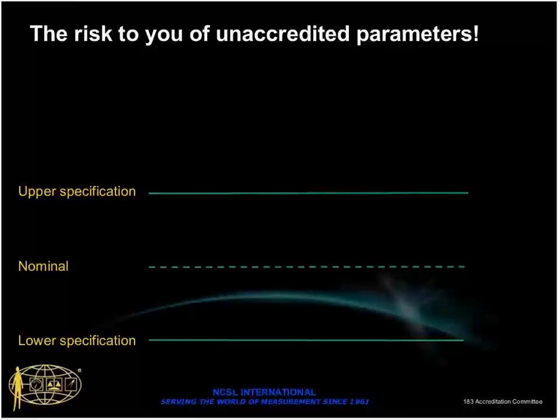Well, thanks, Ryan. So risk is really all about you make a measurement that may be either pass or fail, in other words, measured as observed inside a specification, but in fact the true result may be on the other side of the specification. Formal literature, I think they call that consumer risk. So what you see in front of us now is two measurement results, an A and a B.